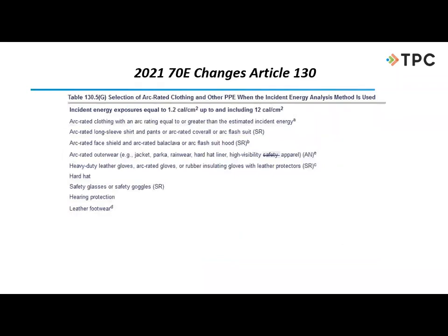If we are using the incident energy analysis method to choose our personal protective equipment, and of course, there's 2 methods we can use. We can use the number 1 preferred method, which is the incident energy analysis method, or we could use the PPE category method. Then if we're using the first method, which is the preferred method, they've given us a couple new notes to this table. So this is just telling us if the incident energy is 1.2 all the way up to 12, some of the PPE that we do have to wear.